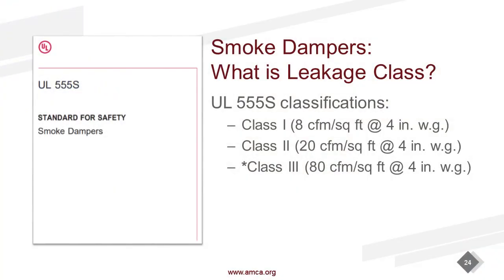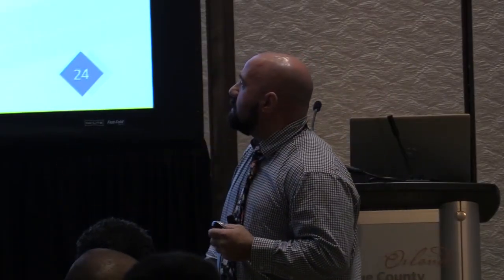So let's talk about leakage a little bit. These are the leakage class definitions from UL 555S. I've got an asterisk there above Class 3. The International Building Code requires a minimum of Class 2 leakage rated dampers. We have Class 3 still in the standard for export. We send them to other countries that don't follow the International Building Code, and there are some applications that might use a Class 3 damper.